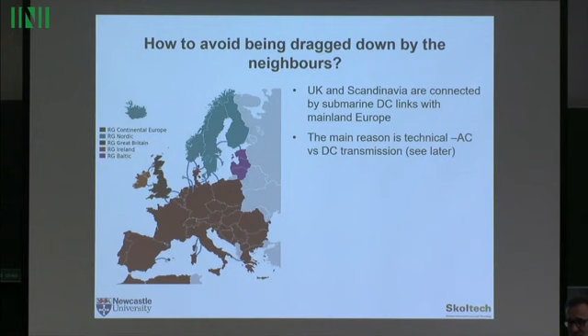The same was true in Scandinavia, nothing happened, because DC links, through their power electronics control, give you exactly the amount of power they're scheduled to give, no matter what. That means frequency control doesn't act across those DC connections, unless you're in Australia, where during one blackout there were actually frequency control schemes working across DC connections, and that caused problems.